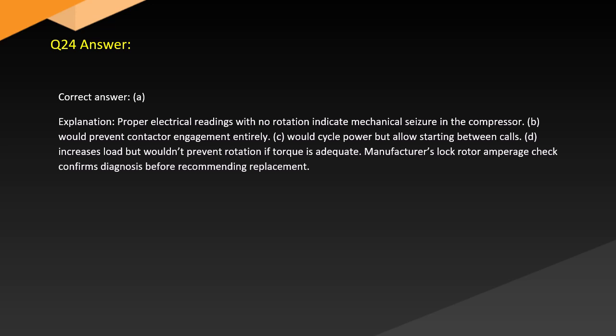Answer. Correct answer: A. Explanation. Proper electrical readings with no rotation indicate mechanical seizure in the compressor. B. Would prevent contactor engagement entirely. C. Would cycle power but allow it starting between calls. D. Increases load but wouldn't prevent rotation if torque is adequate. Manufacturer's locked rotor amperage check confirms diagnosis before recommending replacement.